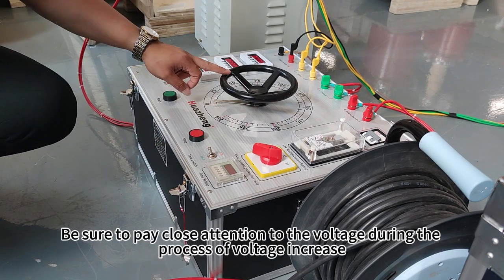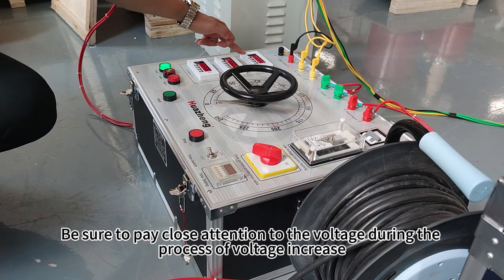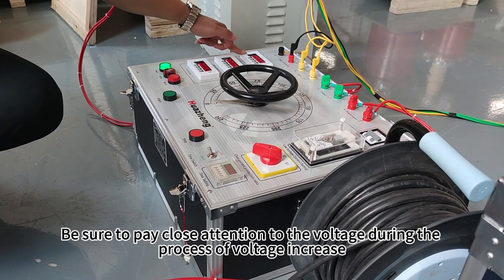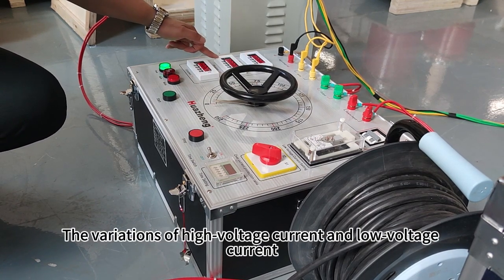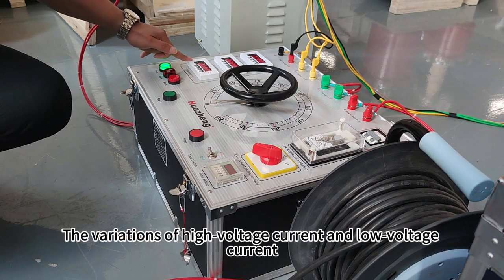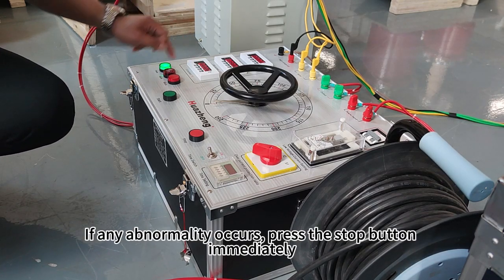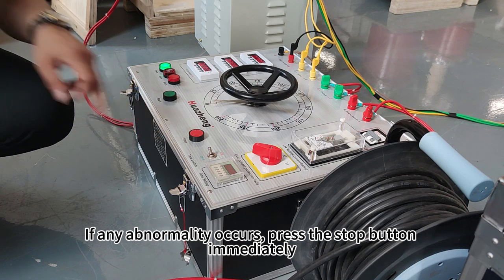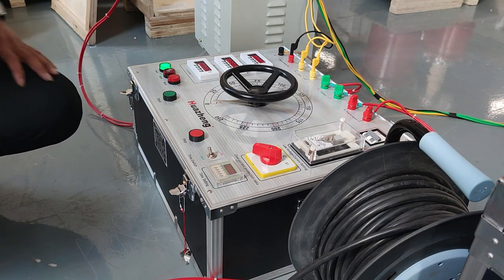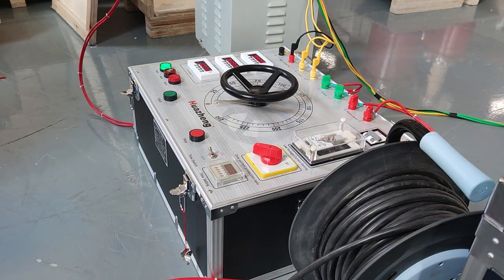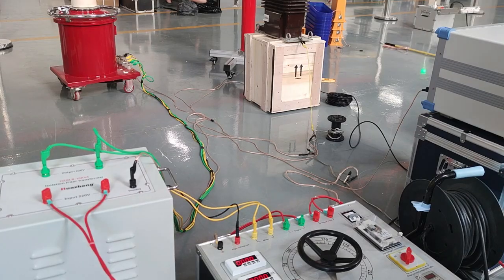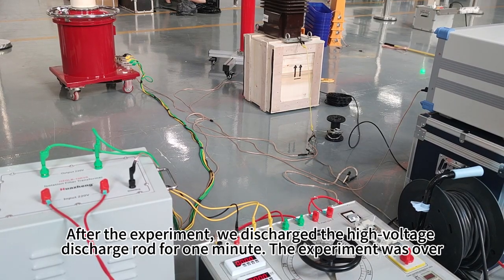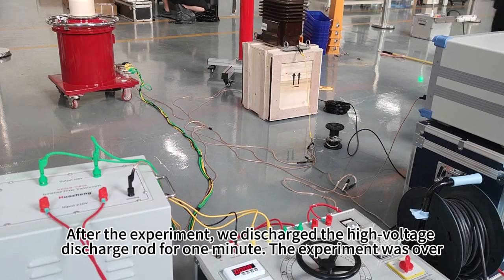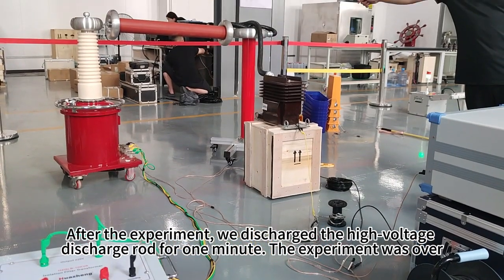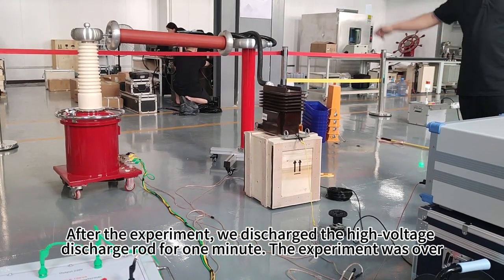Be sure to pay close attention to the voltage during the process of voltage increase, and to the variations of high voltage current and low voltage current. If any abnormality occurs, press the stop button immediately. After the experiment, we discharged the high voltage discharge rod for 1 minute. The experiment was over.